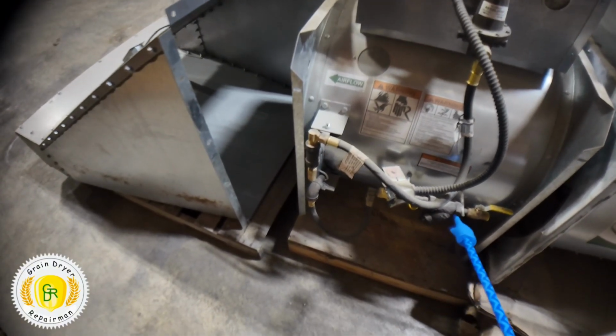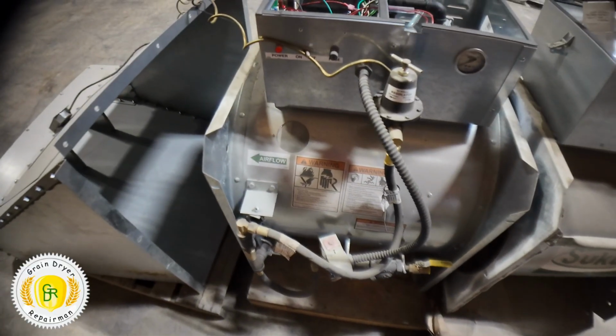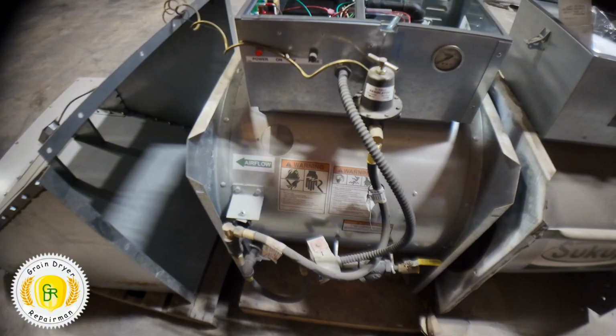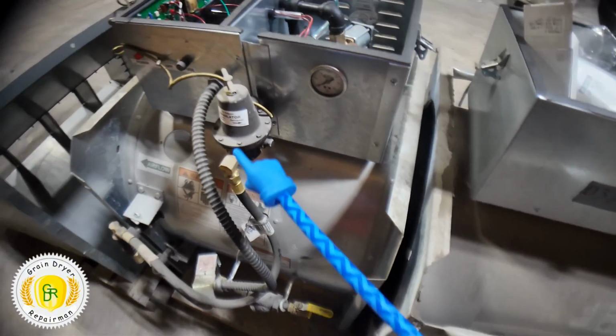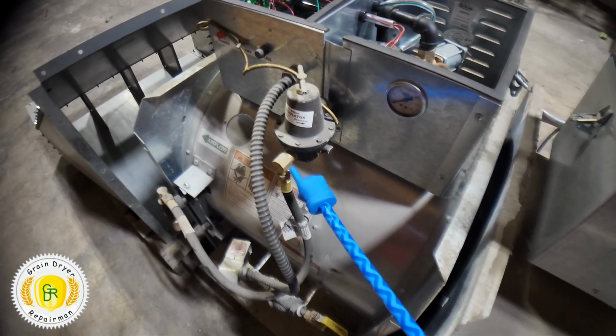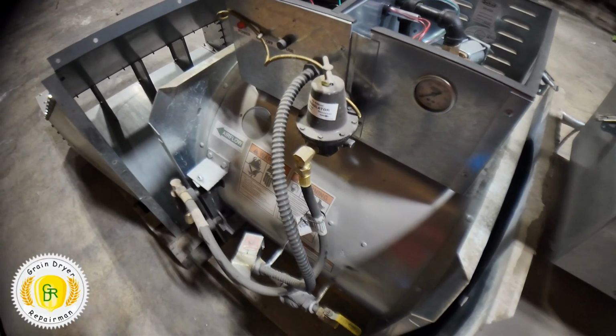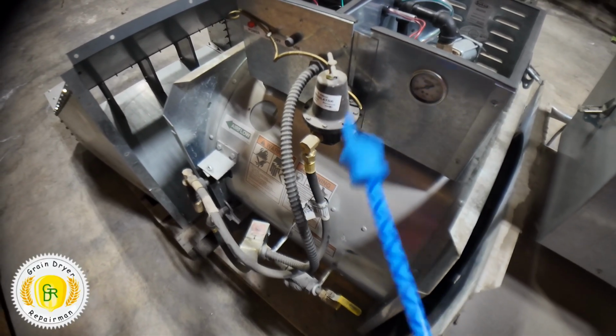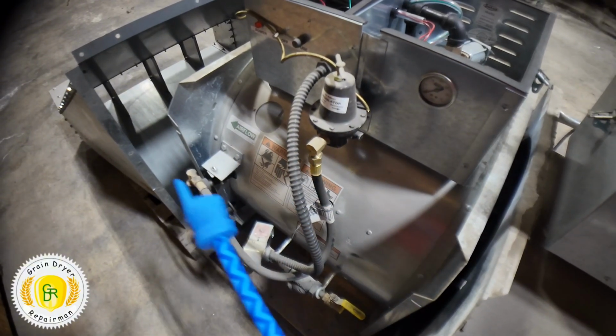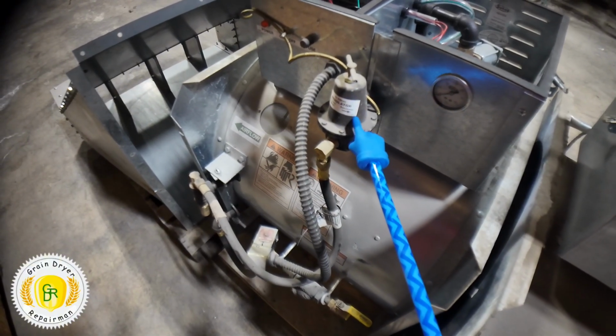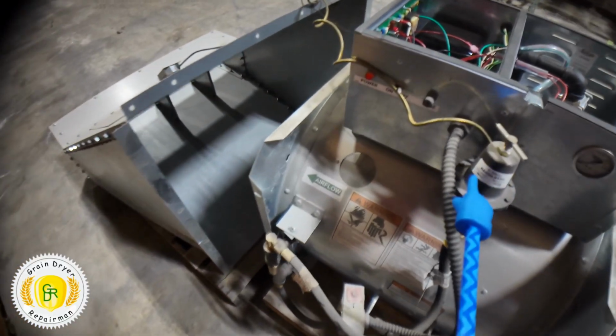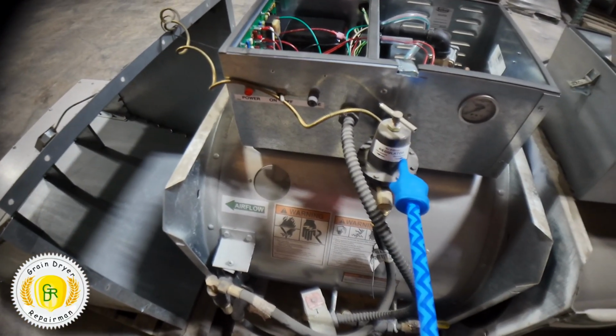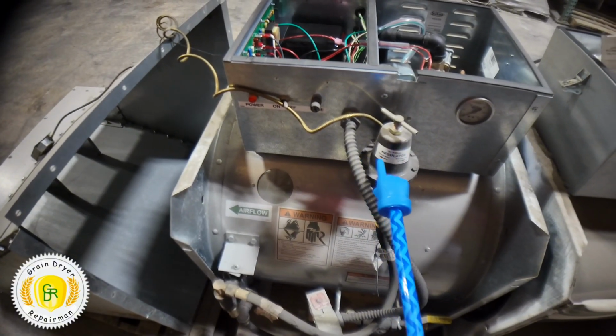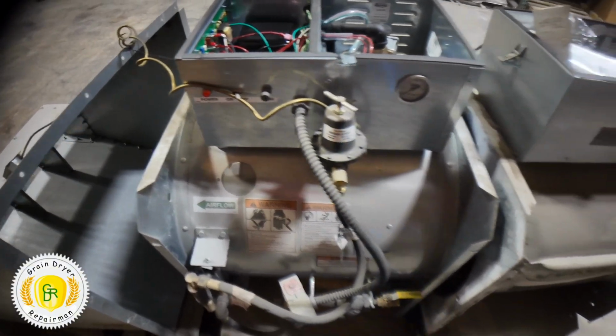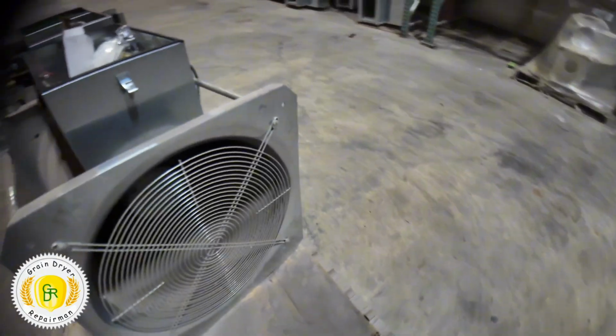If it's a liquid burner, it will have the vapor coil. If it is a vapor burner, it will just have your gas connection right here. Either way, it must have tank pressure. You cannot have a regulator between the propane tank and this regulator. This regulator says increase, decrease. It should say do not touch. That's factory set at 15 pounds, and that is the pressure it needs to be set at.